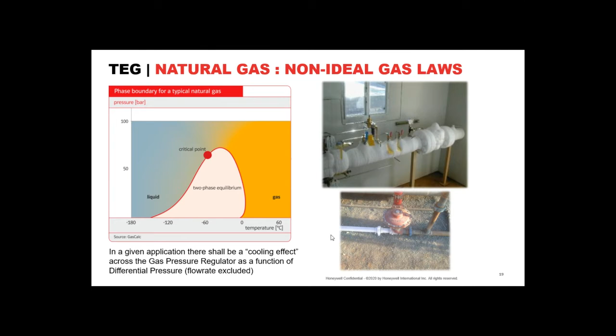What's interesting is that the regulator, the round dish, is dropping pressure, and look at how we've created such a pressure drop that the pipework is chilled and pulled the moisture out of the air. Now we've got freezing, water freezing on the pipe. Amazing contrast when you see the sun's shining on the regulator, the red dome. You can see the shadows from the pipework, and it's a dry, aridy sort of air environment by the sub-base there, but still we've got temperature drop.